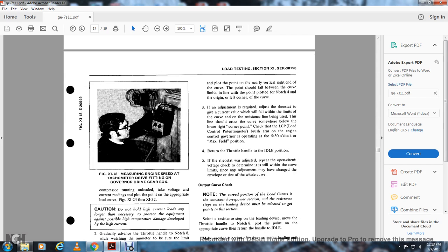Adjustments are required for the rheostat to give a current value that will fall within the limits of the curve of the resistance being used. The line should come across the curve somewhere below the low right corner point. Check the load control potentiometer, or LCP, with the brush arm. The engine governor is operating at the 5:30 o'clock position with the maximum field position.